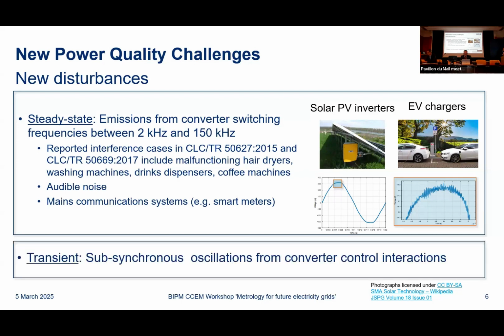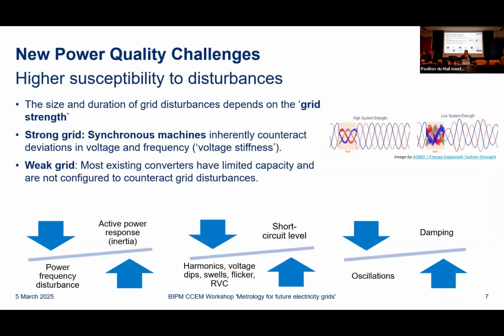I'm also going to touch on another type of disturbance that we're seeing increasingly in the grid. They are of a more transient nature, but they also affect power quality in the sense that they can push the voltage waveform outside of the parameters it should be in to ensure good functionality of the grid. There's a new type of these oscillations that originate particularly from power electronic converters, so I'm going to touch on that as well. So we've got two new types of disturbances, but then we also have what I call here a higher susceptibility or sensitivity to those disturbances.